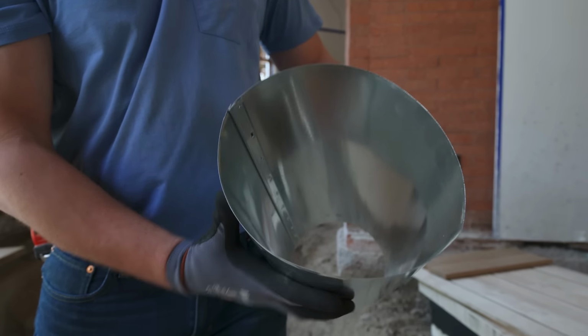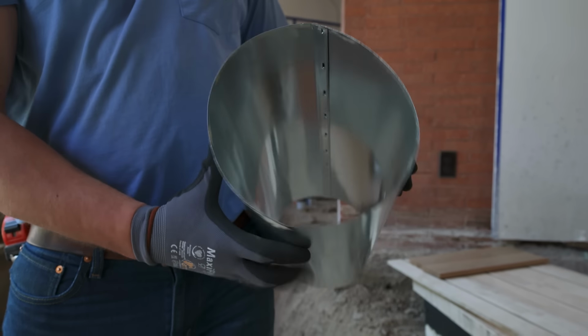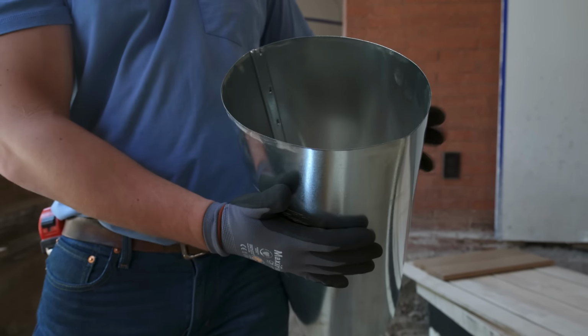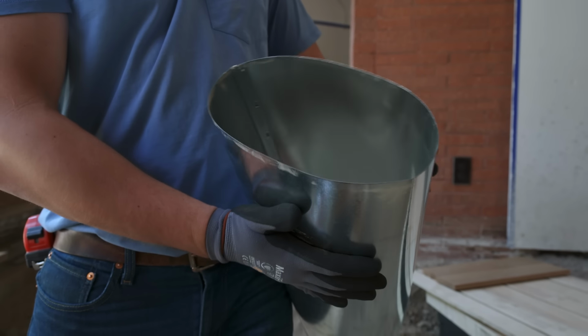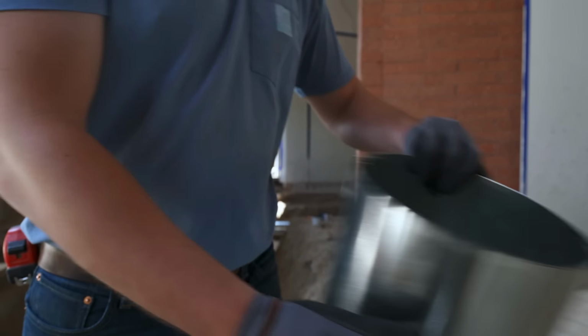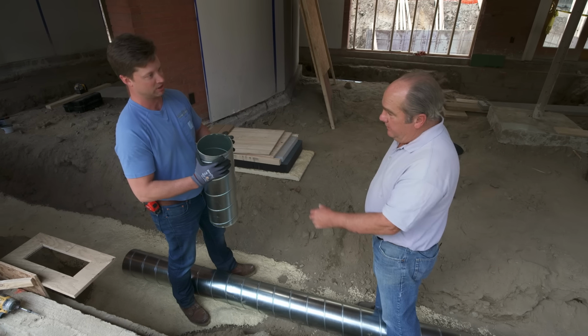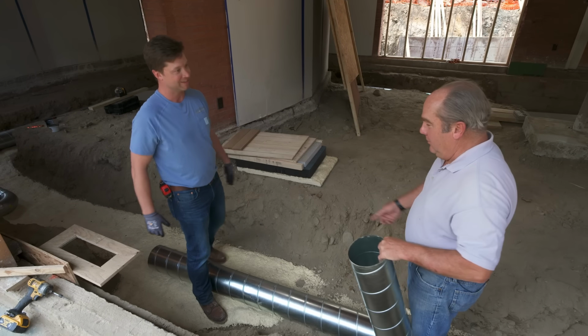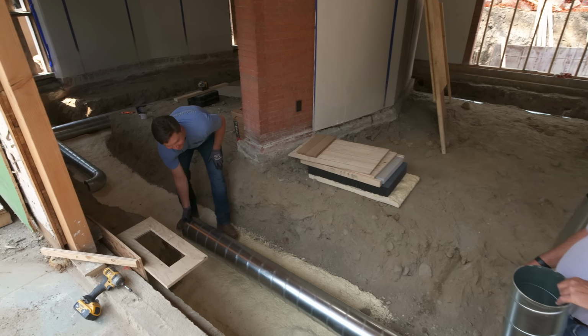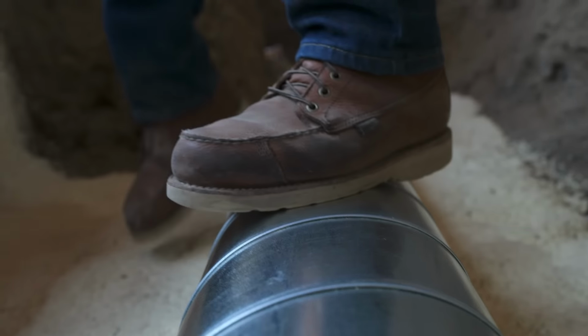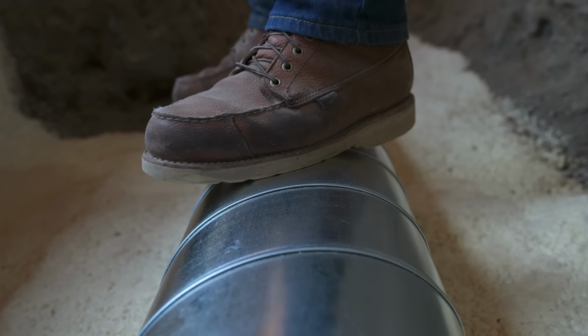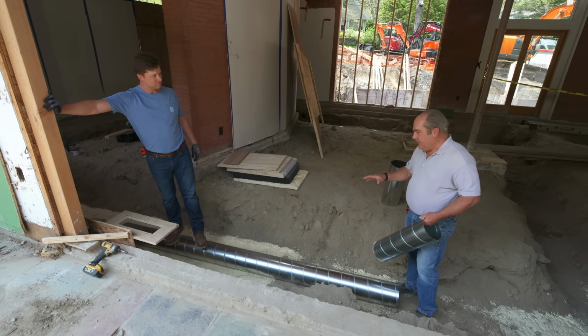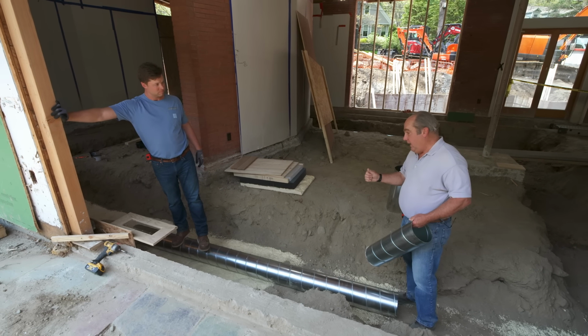This duct is what we typically use in a house, 30 gauge galvanized metal, and as you can see, the weight of the concrete would just crush it. There's no strength at all to that. You put concrete on it, it'll crush like nothing, fall right apart. This spiral duct is double the gauge thickness and has a seam that adds structural integrity. You could stand on this and it's not going to crush. It'll last a lifetime. So we know it's going to be structurally sound, but we also need to make it dry and insulated.